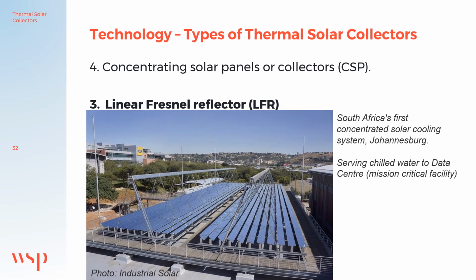As mentioned, the relative simplicity and lightweight of the LFR allows it to be easily installed on flat roofs. This photo was taken of South Africa's first LFR, and the hot water is used to drive an absorption chiller that generates 6 degrees Celsius chilled water, or 42 degrees Fahrenheit, feeding a mission-critical facility or data center. This client is MTN, which is equivalent to AT&T. They are South Africa's second largest telecom company. They are pioneers of renewable and alternative HVAC systems in Africa. I'm also proud to say that I was the designer for Africa's first tri-generation plant that integrated into the same system.